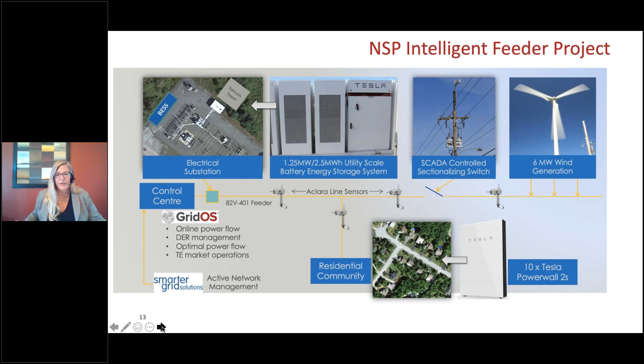This is the power pack located at the substation. There are 25 Tesla power pack battery cabinets and 2 inverters installed. Because it's located in a substation, we had to have utility grade connection equipment: step-up transformers, an underground switch to an overhead primary disconnect switch that's motor operated and operational from our control center. We also, because we're operating the system as a microgrid, had to have a grounding transformer that provides a neutral reference when we are islanded.